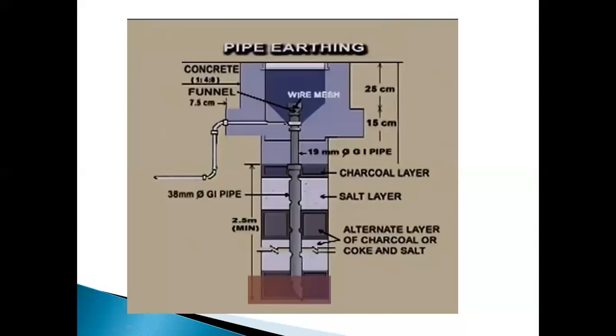The purpose of adding coke with the salt is to decrease the earth resistance. This galvanized iron pipe is connected to another pipe whose diameter is 19 millimeter and length is 1.25 meter, by means of a 38 into 19 reducing socket. A funnel with wire mesh is fitted at the top of the 19 mm pipe and is fastened in a cement concrete structure.